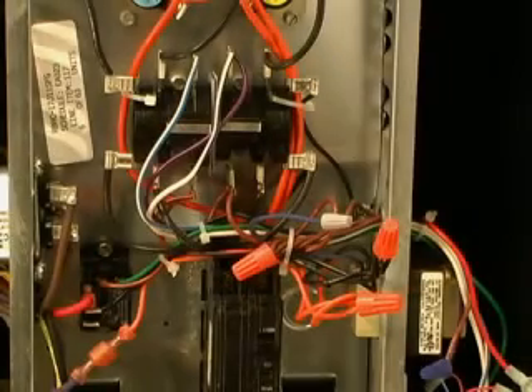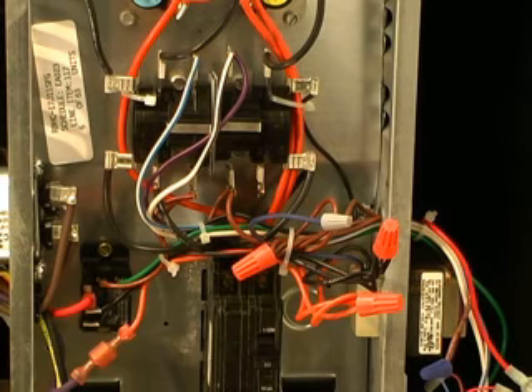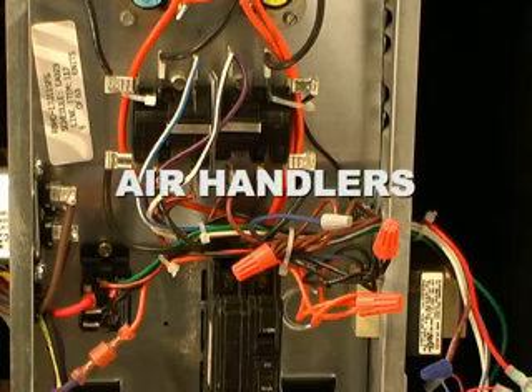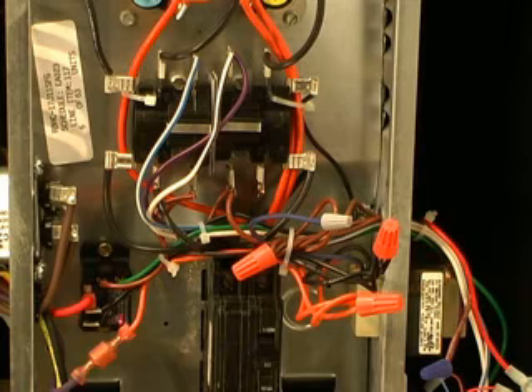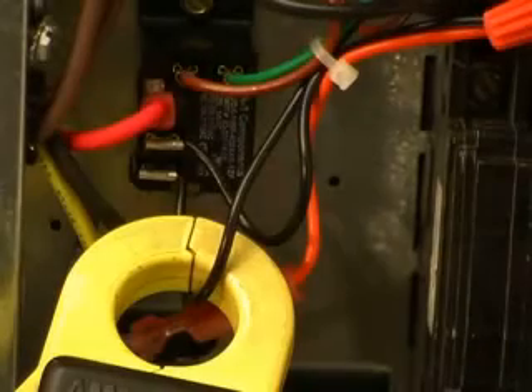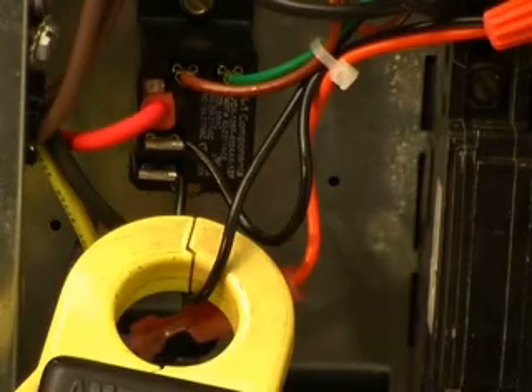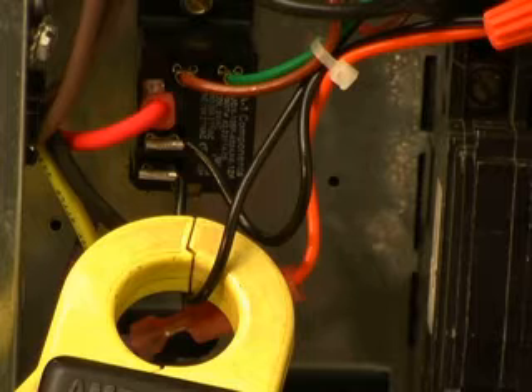The most common problems you have with these air handlers are the relay, the blower motor relay, or whatever type control it is. It may be a little time delay, solid state thing, or something else. But they either fail to turn the motor on or they fail to turn it off. And then the transformers, fairly regular.